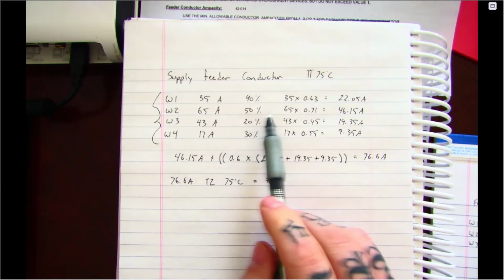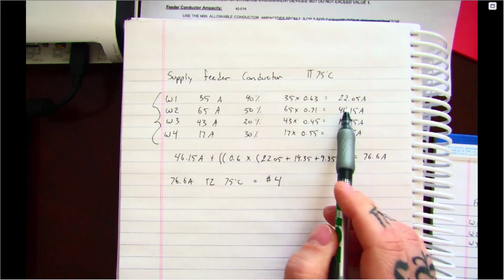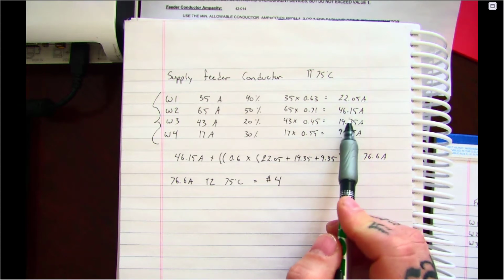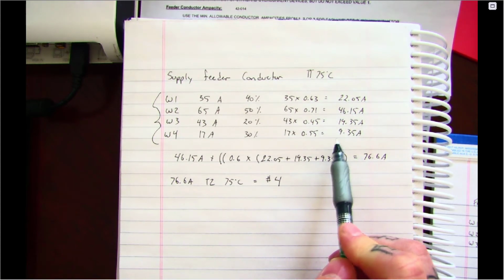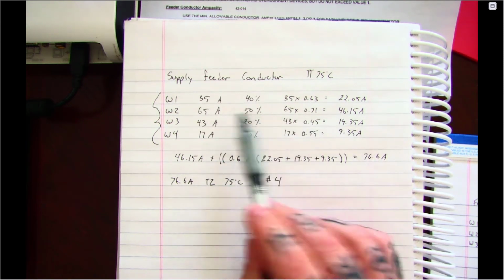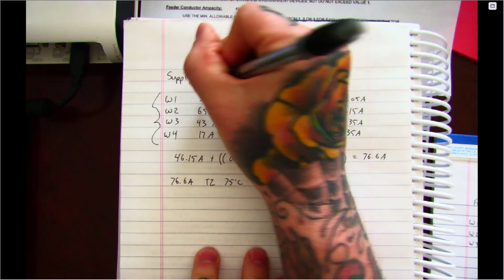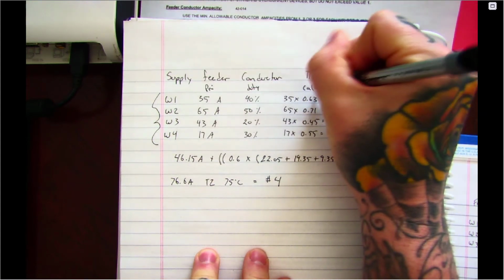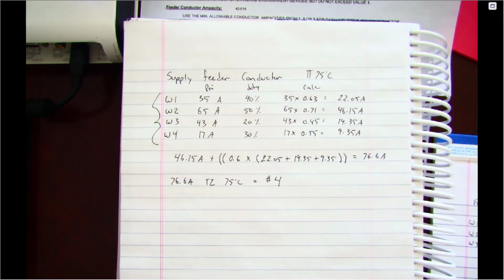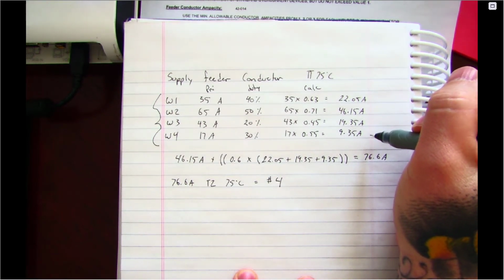So again, in our question on Blackboard, we've given you this. It's basically everything that we just did in the previous question for sizing conductors. We don't have the conductors listed here, but these are the values of current that we would go to find our conductor from. And we don't happen to need those conductor ampacities, so we don't have them listed here. But we would take these, again, this is my primary, this is my duty, obviously my calculation. Okay, so that's where we're getting all those numbers. We need these calculated numbers though to find out the size of the primary feeder conductor.